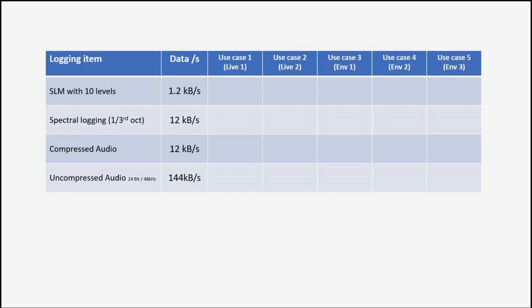I have prepared a list of typical use cases and added the memory consumption for each data logging case, assuming that you want to have a set of measurement data every 100 milliseconds. This table shows if we record sound levels with typically 10 levels, it will occupy about 1.2 kilobytes per second. In case we are adding spectral information, in this case with 1/3rd octave resolution, the data usage will be another 12 kilobytes per second, representing about 10 times more than wideband levels only.